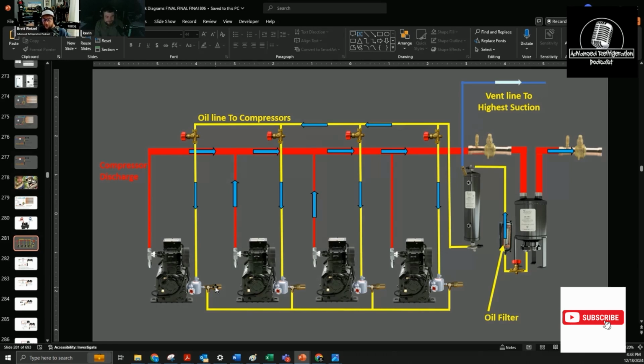And like I told you the one night, I had one that, literally, I shut off the main valve to change out the oil filter. When I did that and went to do something else, 2 compressors instantly failed. It was like a minute and a half. It just railed out that oil. That was the one where every single compressor was shot in the rack. Yeah, that's wild.